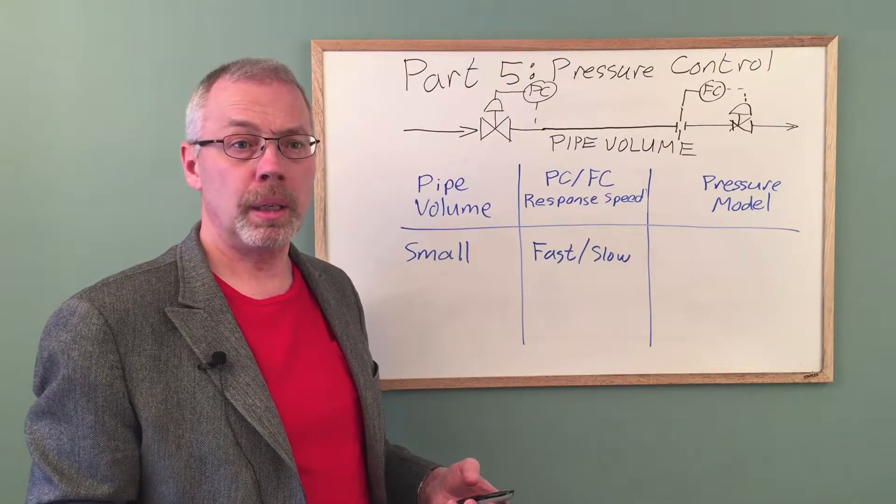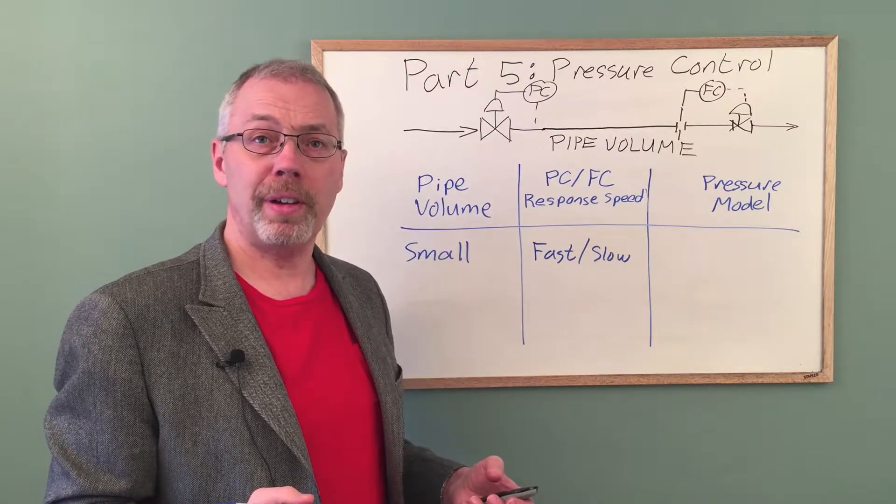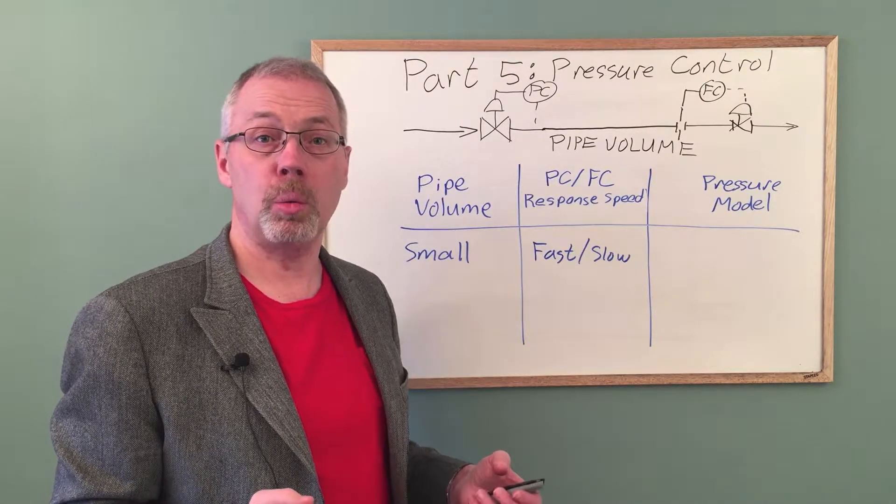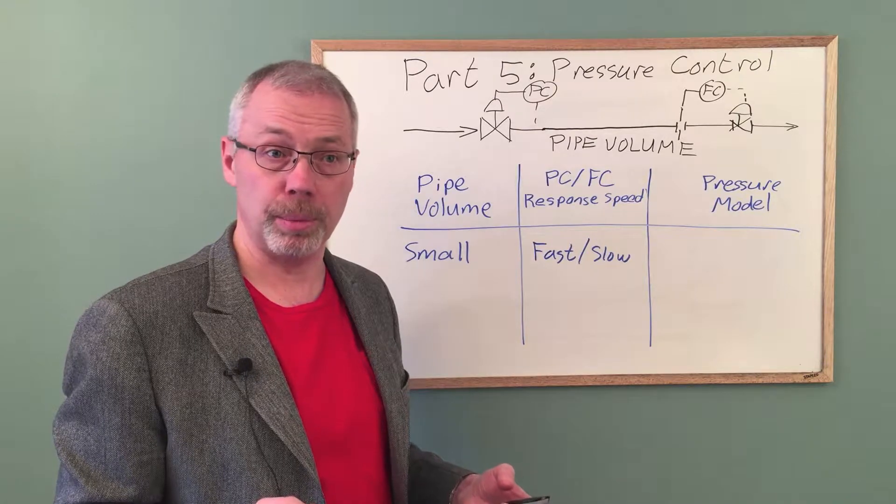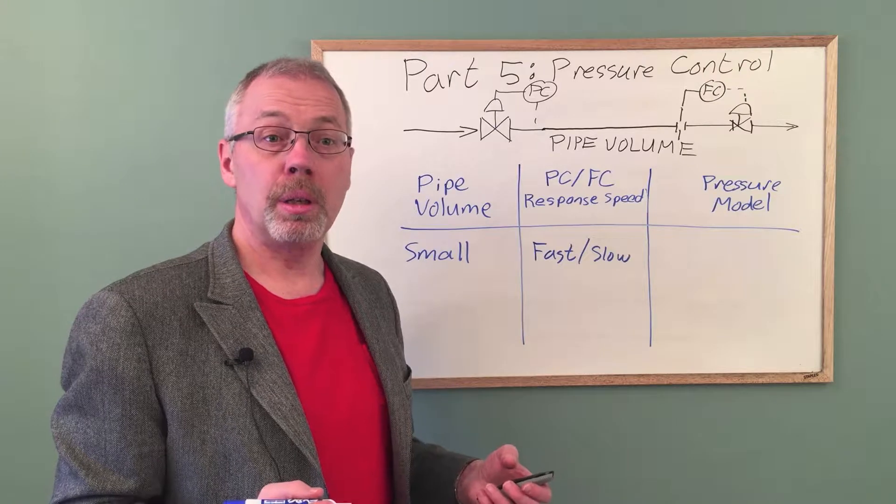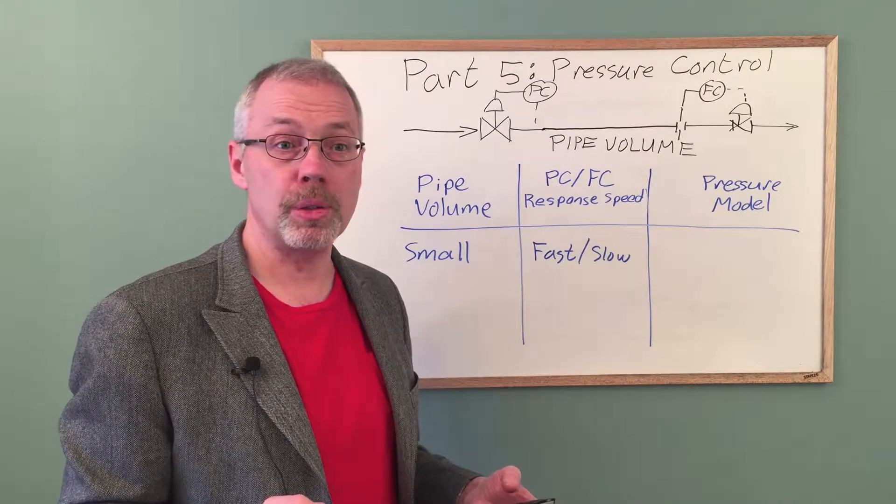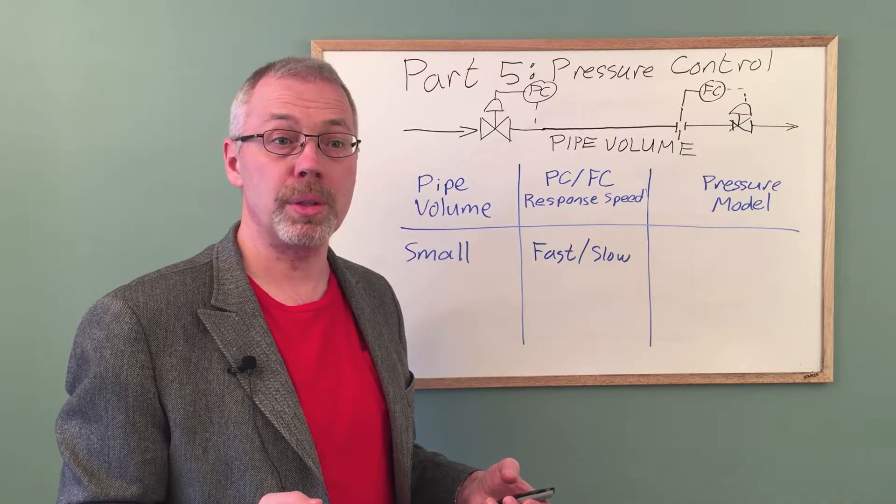How will the pressure respond? Since the flow controller is slower, let's assume that the flow valve position does not change while the pressure controller is in action. The pressure valve opens up and admits more fuel gas. The pressure in the pipe volume increases and the outlet flow increases. Everything levels out to a steady value.